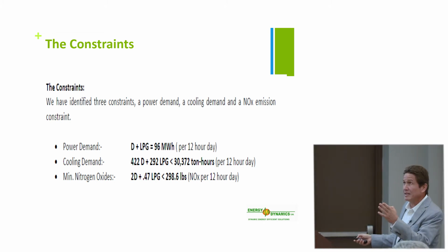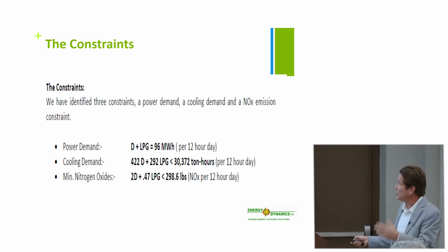And then the nitrogen oxide - you have to watch the pollution. Jamaica had some laws in terms of pollution. They want 2 times diesel plus 0.47 times LPG to be less than 298.6 pounds NOx per 12-hour day. And when you put that into the equation, a simple spreadsheet, Excel could do this thing for you.